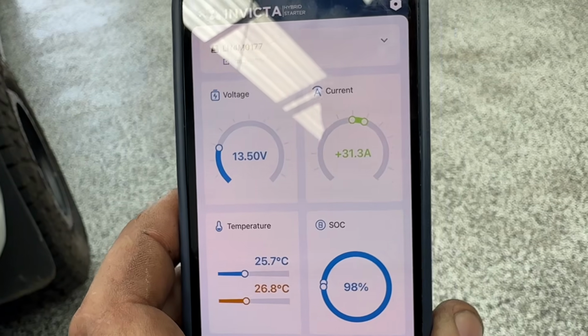Obviously under load that alternator will put in a bit more than that. So we spoke about amperage there. The fridge is only going to pull at max 4 amps worst case, maybe a bit more if it's hotter outside, but somewhere around 4 amps. The fuse in there's only about 6 amps anyway, so it's not going to pull more than that. The wiring's not rated to any more than probably 10 amps, to be honest.